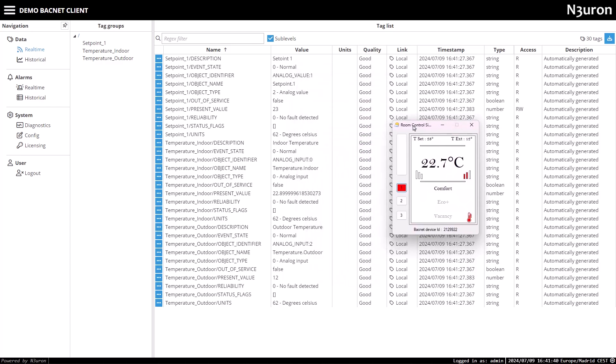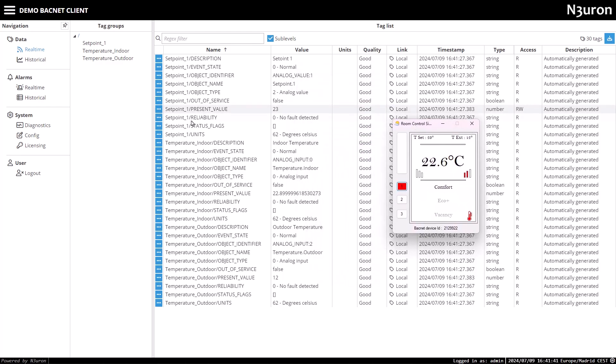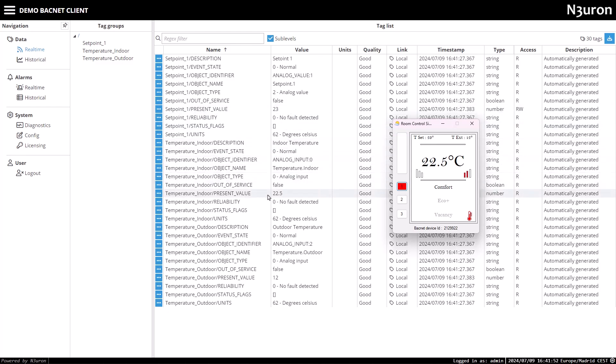Then I'll open the room controller 01 device visual interface. Here I can confirm that the setpoint1 present value, temperature indoor, and temperature outdoor present values are displayed with the same values as in the real-time screen in N3uron.